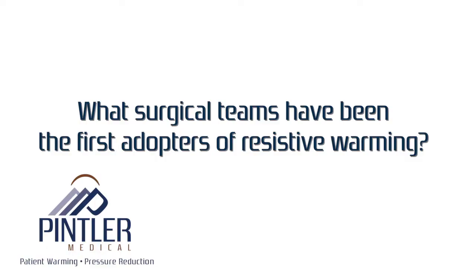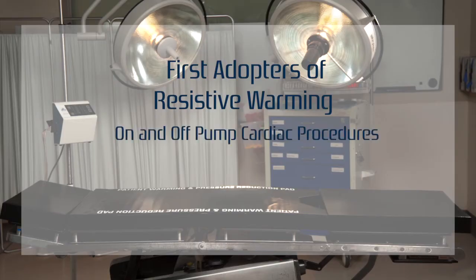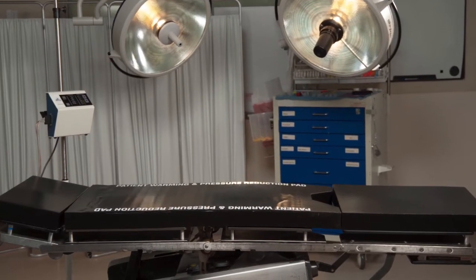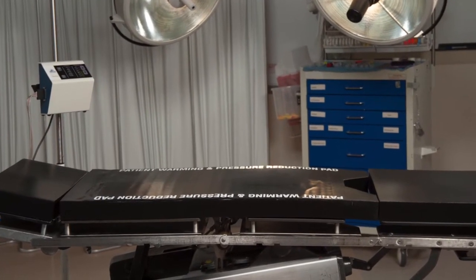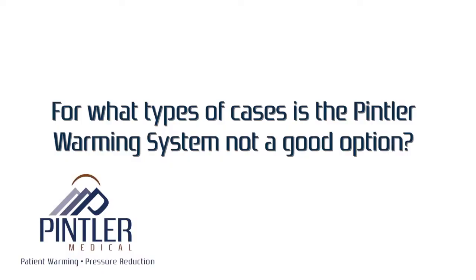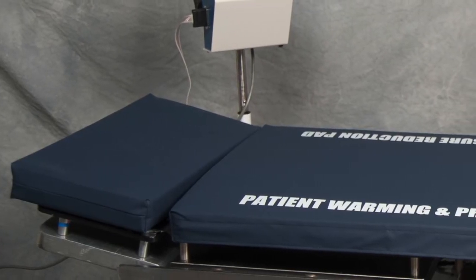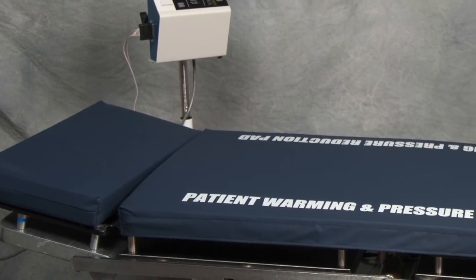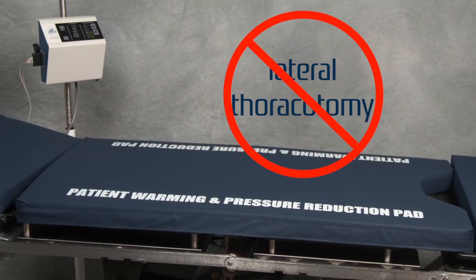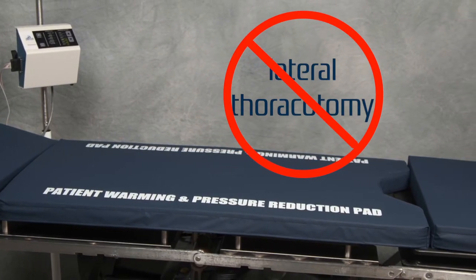What surgical teams have been the first adopters of resistive warming? First adopters include on and off cardiac procedures, transplant teams, and orthopedic surgeons. With the evolution of skin and surgical site infection concerns, more general procedure rooms are adopting warming and pressure reduction for all patients. What type of cases is the Pintler warming system not a good option? A patient must be in contact with the pad for it to effectively warm. Surgeries like lateral thoracotomies where the patient is on their side supported by a bean bag are not a good option.